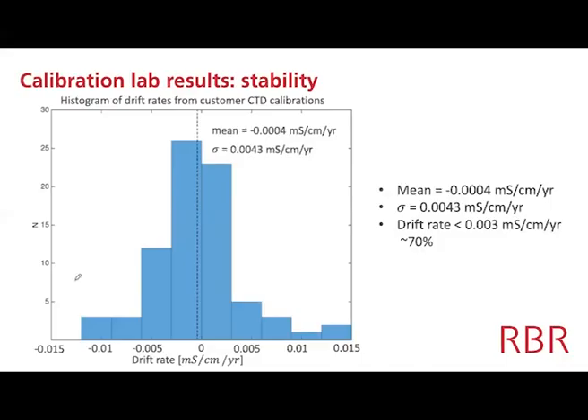A bit about long-term stability of the sensor. Instruments are routinely sent back to RBR for calibration, so we can estimate a drift rate from that. We can just take the data of 2 successive calibrations, calculate an error, and divide by the time between calibrations to get a drift rate. So here there's 100 or so instruments, perhaps. And what we're plotting is a histogram of drift rate from these instruments that have been returned to RBR for calibration. The average is quite close to 0.